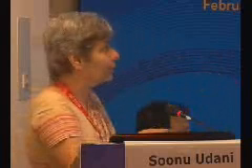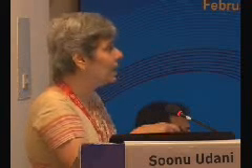And that is how you try to limit your pressure, but at the same time try to achieve your targeted volume. Now in this one, you cannot do it within the breath. Here it goes over 2 to 3 breaths, and now with the Servo-i, actually the algorithm says that it even does it breath by breath, and it's a much faster algorithm. But at the same time, you don't have all your breaths looking different.